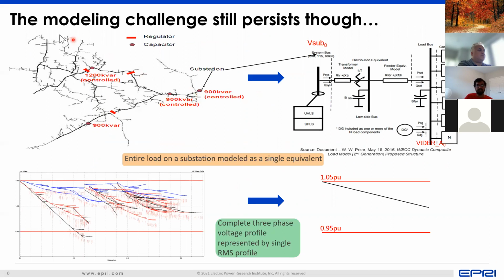Because this is how one feeder may look in the distribution network. This is just one feeder, and remember that in a network the size of, say, the Eastern Interconnection in the US or the Western Interconnection, there could be more than 10,000 such feeders connected in the network. So we don't want to be representing each of them. But an actual feeder has things like regulators and capacitor banks, which control the voltage.